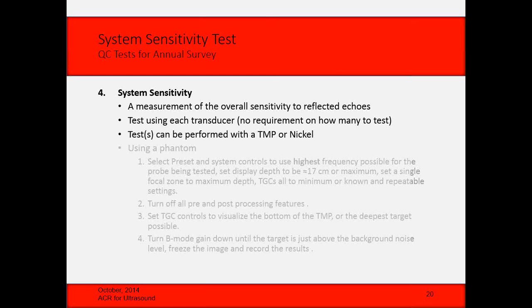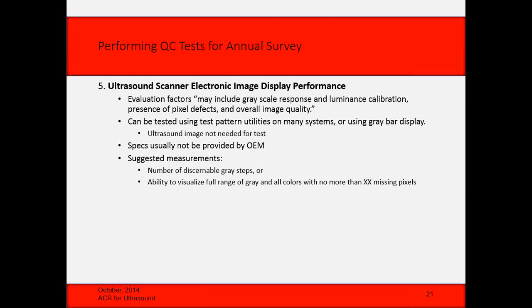The manufacturers typically don't give us any specs for this, and they don't give us specs for too many things except electrical leakage usually. So some of the suggested measurements for this is the number of gray steps that you can see, or your ability to visualize a full range of gray in all the colors with no more than so many missing pixels. There are some standards out there for this that you can try to adopt one. ACR suggests using this standard, the ACR AAPM SIIM technical standard. They suggest using that for additional information on tests and testing methods.